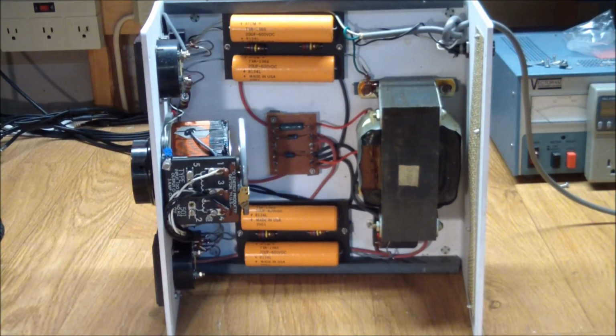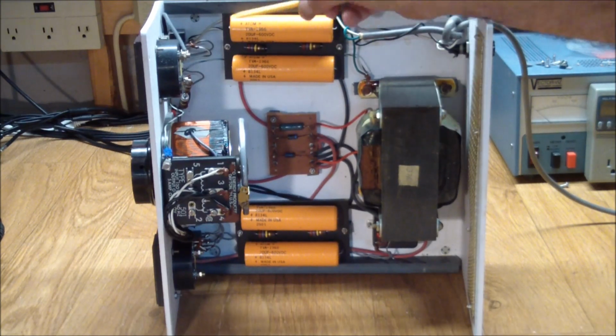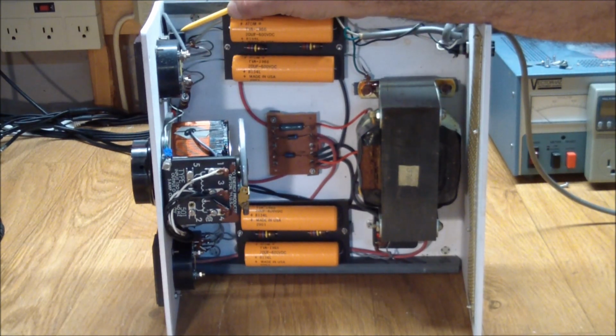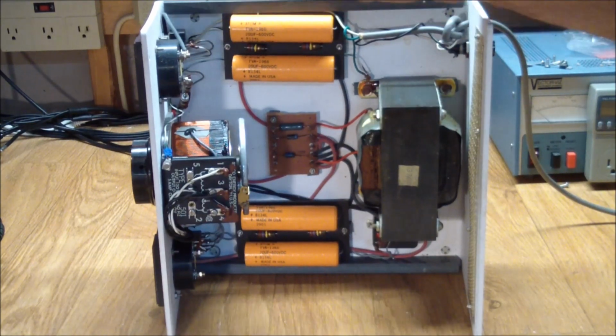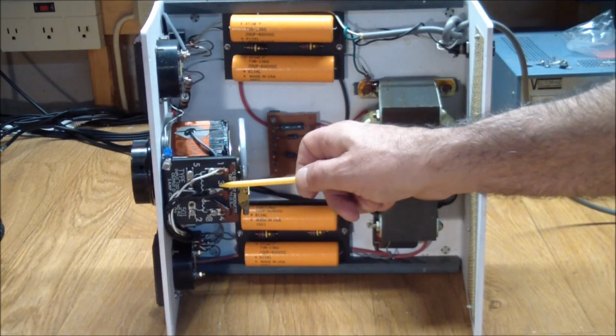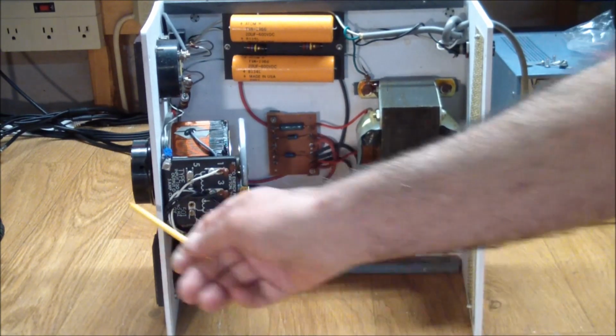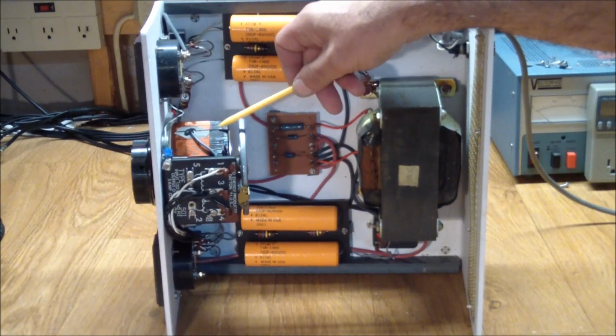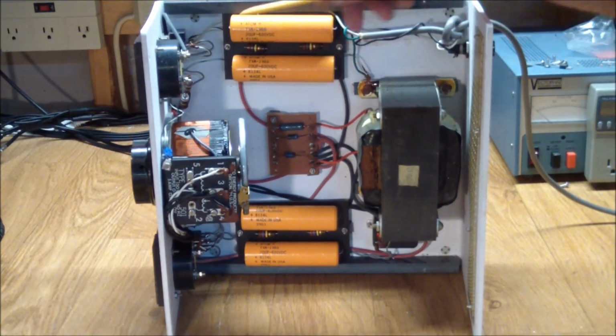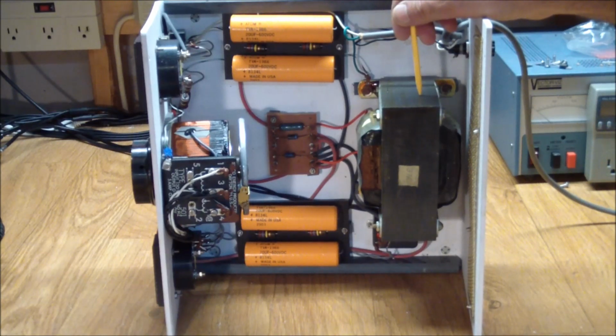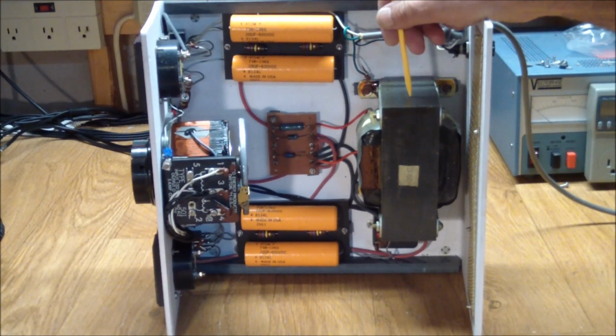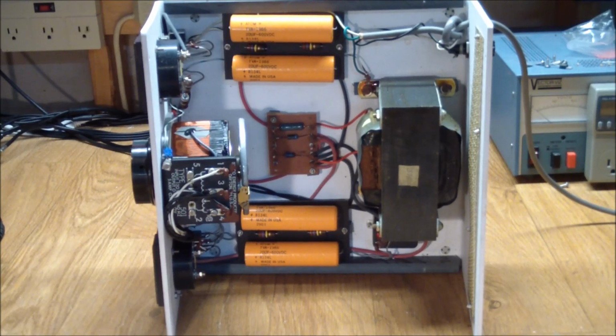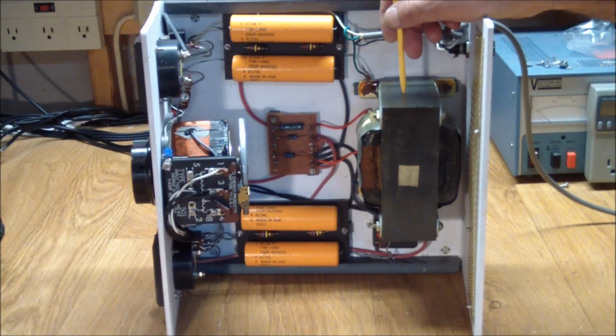So the AC comes in, and it travels through the massive power switch over here, which in turn feeds the AC to this auto transformer, or variac. The dial in front changes the turns ratio in the variac, and that in turn is fed to this large transformer, large and heavy. These two are probably why this thing is so heavy. It's a step-up transformer, so it takes the input, which should be between 0 and, in my case, 120 volts, and steps it up to between 0 and 2000 volts.